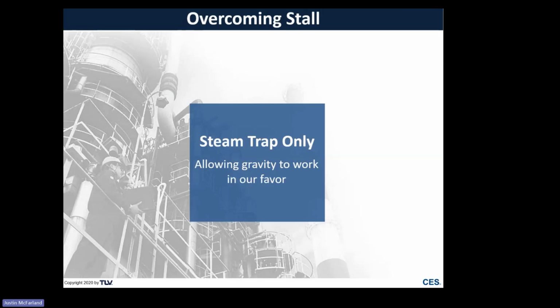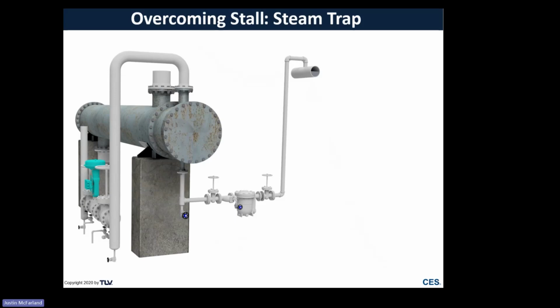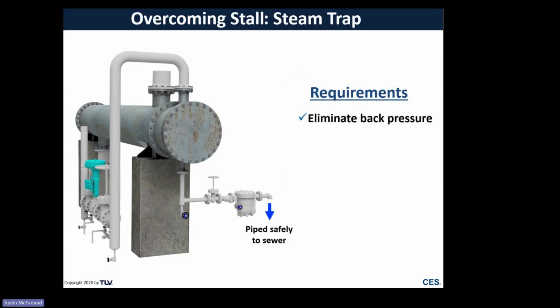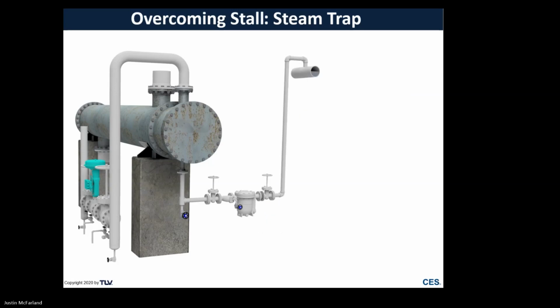So the big question is, all right, I hear about this stall. I hear it's a problem. I recognize all the suboptimal symptoms that you've said. What can I do to overcome that? Well, there are some easy options and some more complex options. The easy option is using a steam trap only and allowing gravity to work in our favor. So here's our process heater again with our inlet control valve and our steam trap. What we need to do is eliminate the back pressure. So if you didn't see that, we've got condensate that is discharging overhead to a pressurized return.